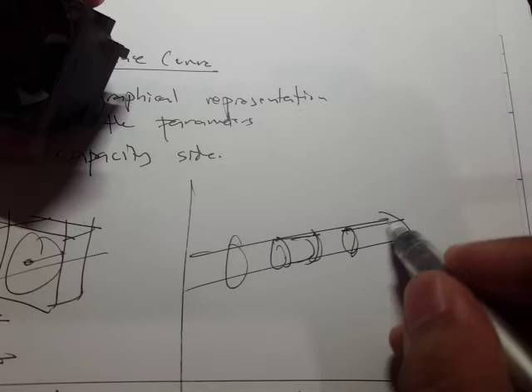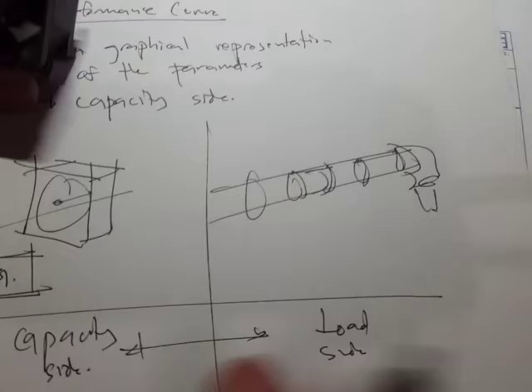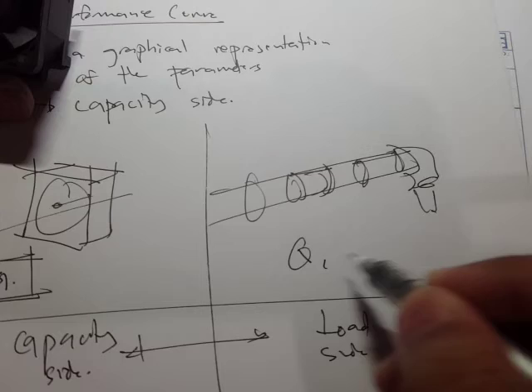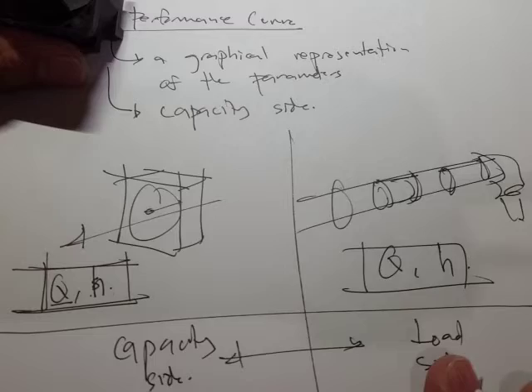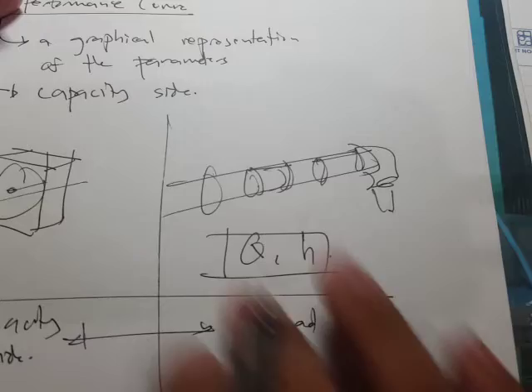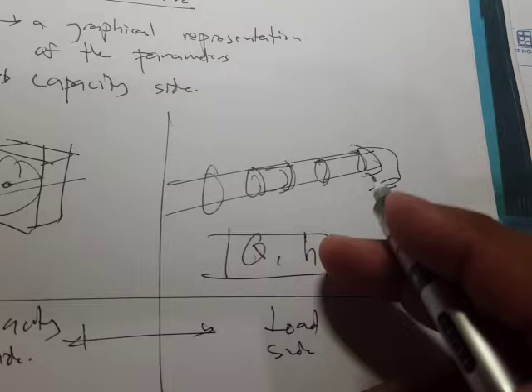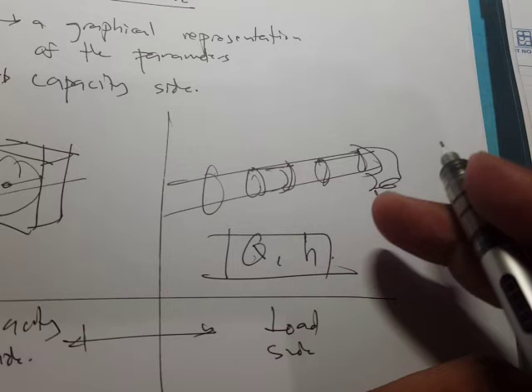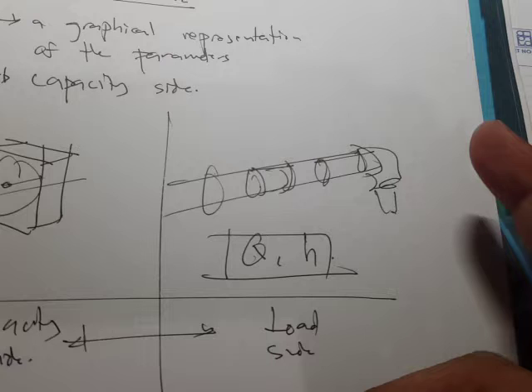For example, if I want to install a fan into a ducting system with filters, equipment, and bends, that's the load side — it will have a required flow rate and a required static pressure. When selecting fans, we compute the required flow rate based on the application, such as a livestock building or residential and commercial buildings, based on the ventilation requirements of the occupants.